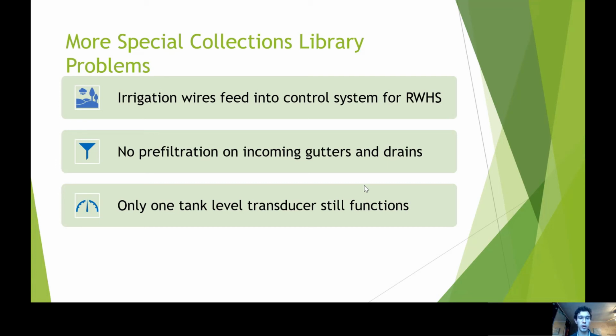The consequence of the last point is that it indicates there is no level in one of the two tanks, so water is currently only drawn from one tank, and they're relatively expensive to replace. At the moment, the system is turned off. It is valved off and no longer being used, and after discussion with the grounds department, it appears that there's no longer a need for the system. So despite the fact that all this money and all this infrastructure is in place, the system is not being used because needs changed over time.